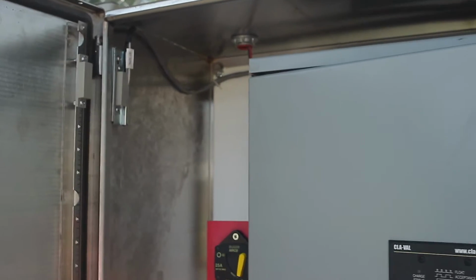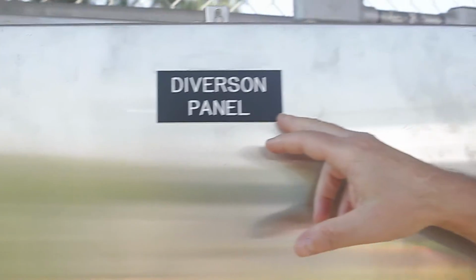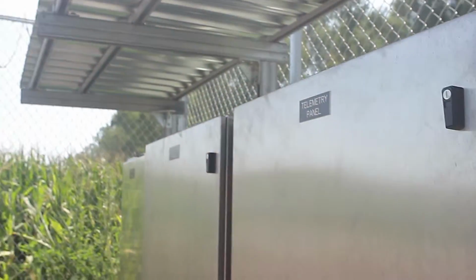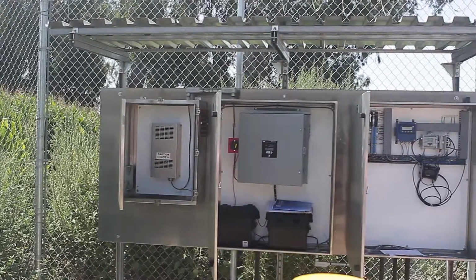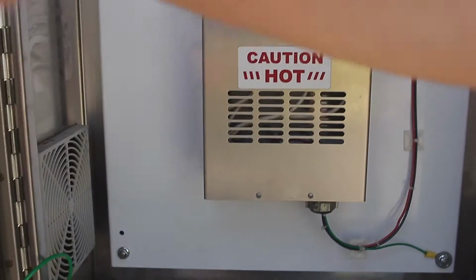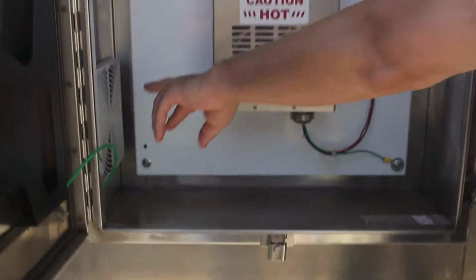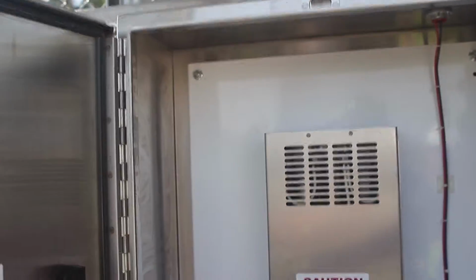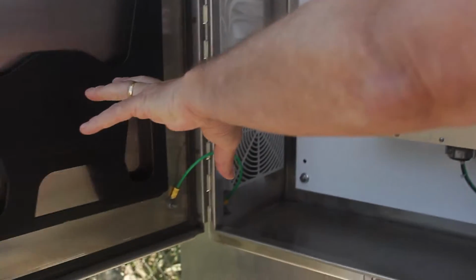We want to cut to the diversion load on the next panel. That should be in a separate panel because it generates heat. Okay, this is the panel just right next to the main control panel. That is the diversion panel. One thing I do like, they have a sunshade here. That's a very good idea to protect from elements, rain and whatever. As you can see, this is obviously not a waterproof enclosure. It's inside an enclosure that is vented, so the heat will have a chance to pass out of this panel.